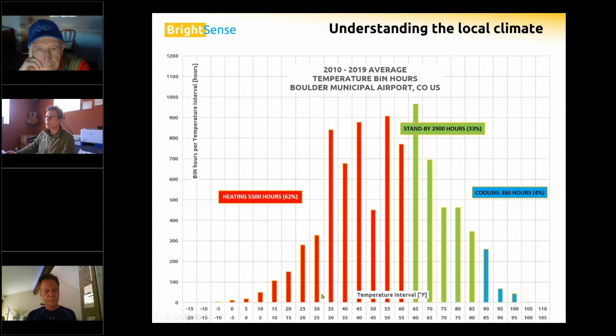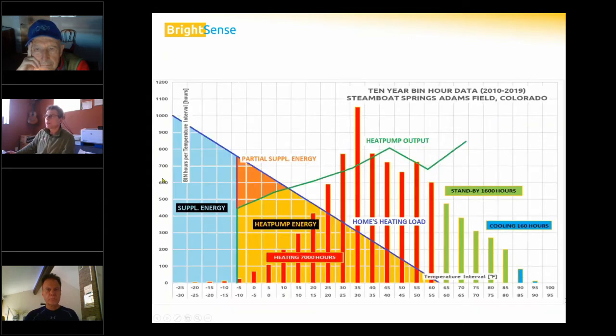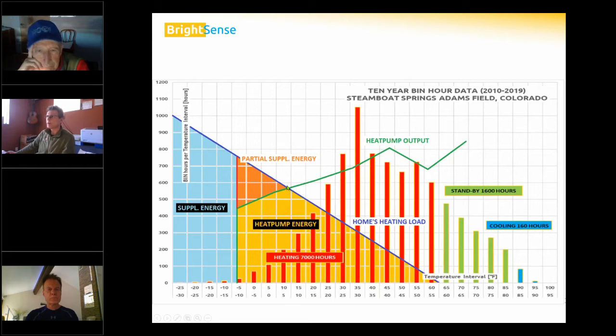In that temperature range, our heat pump — if we remember the performance curve — operates really well at really high efficiencies. Here's the same chart overlaid with heat pump performance. If this is our balance point at around 10 degrees, we can determine how many hours per year of supplemental heat we need to support the heat pump when it's no longer able to keep up.